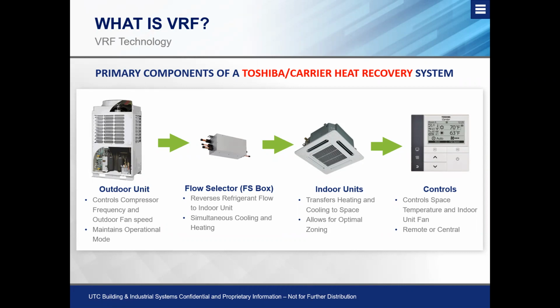Okay, the biggest difference between the carrier two-pipe and the Toshiba carrier three-pipe is that on the heat recovery systems, that outdoor unit for the Toshiba models is where that heat exchange for that separation process takes place. Hot gas, liquid, or suction. And essentially all that happens in that outdoor unit is a solenoid valve on the hot gas line opens up and bypasses that outdoor coil where we send it in a cooling mode. And now it redirects it directly to the hot gas line, which leaves our outdoor unit and feeds into this flow selector box. So that separation process on the Toshiba carrier happens at the outdoor unit, not at the flow selector box.